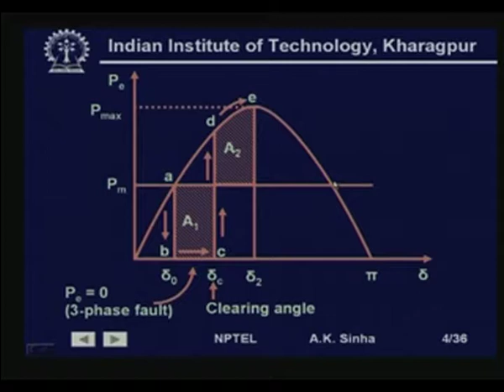If delta 2 goes beyond that, then the system becomes unstable, because in that case the accelerating area is going to become more than the decelerating area, because the maximum decelerating area can be available only up to this point. The same case is shown in this figure. What we have done is we have taken more time for the circuit breaker to open, that is, for the fault to be cleared. So, if we clear this fault around this point, then we will get the decelerating area maximum up to this point, and if this A 1 is equal to A 2, then we have a limiting condition for transient stability, that is, delta 2 is now equal to the maximum delta which is possible under this situation. We call this angle for clearing the fault the critical clearing angle, because if we clear the fault after this critical clearing angle, then the system becomes unstable, and we must clear the fault before this delta CR for the system to remain stable.